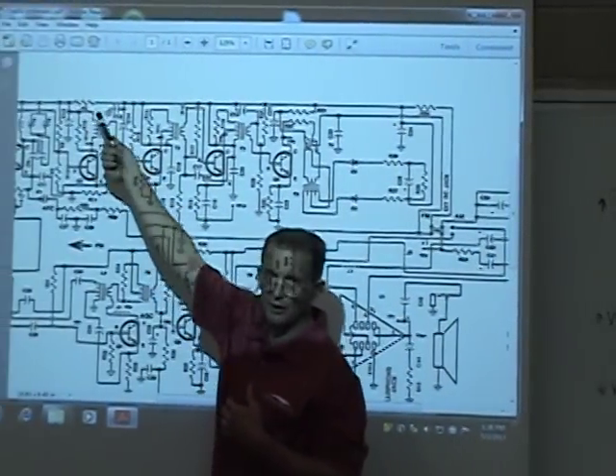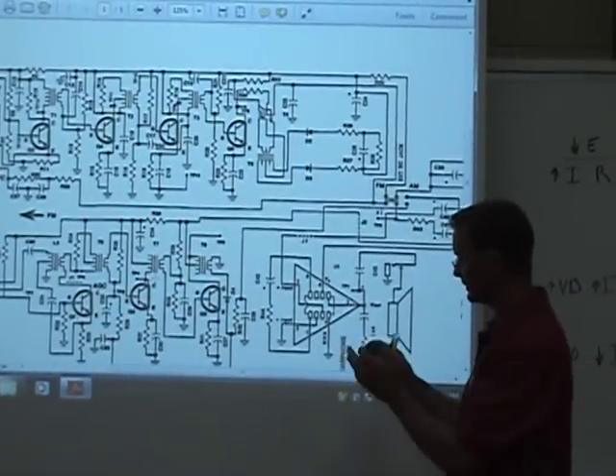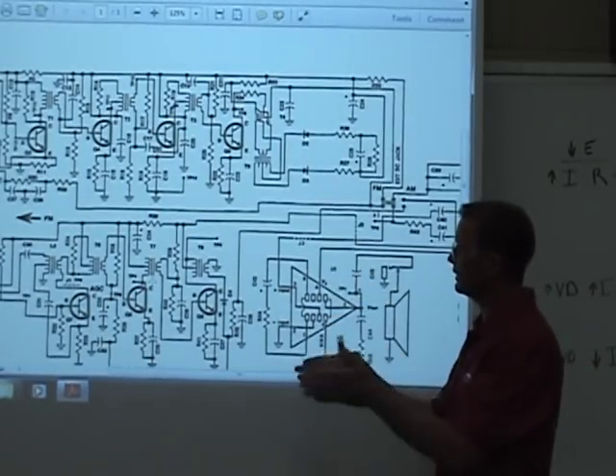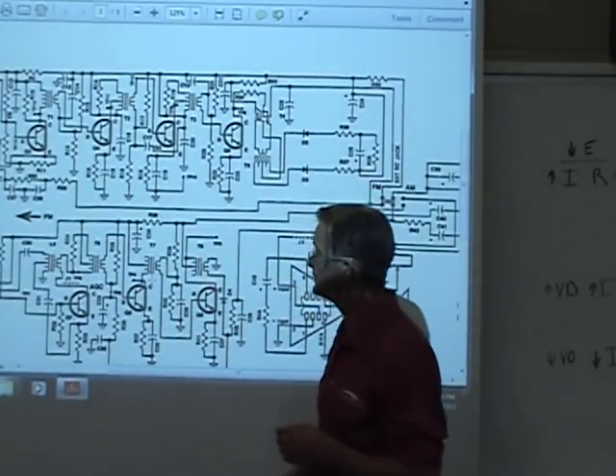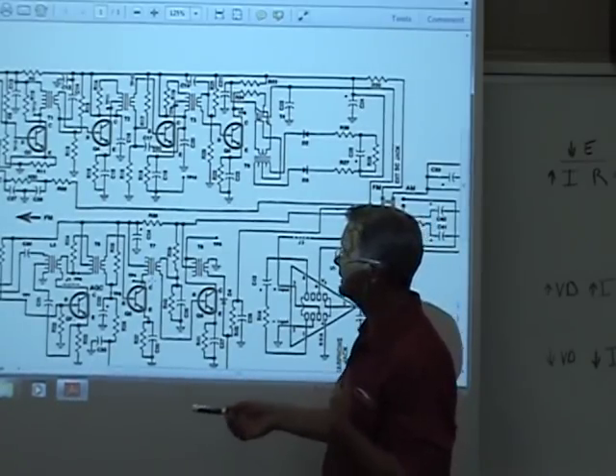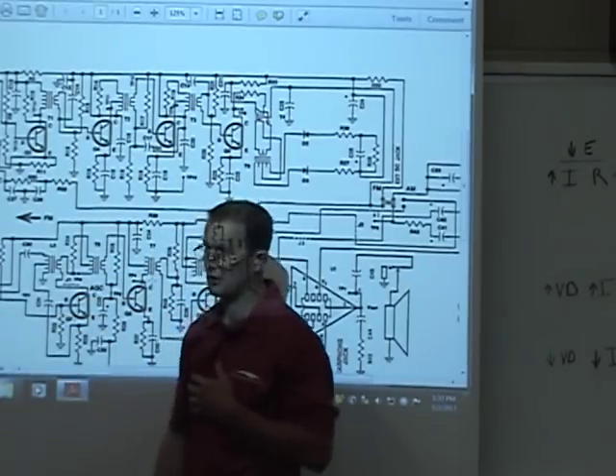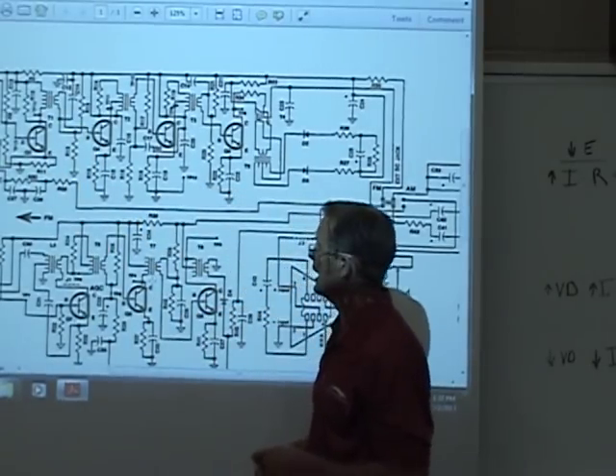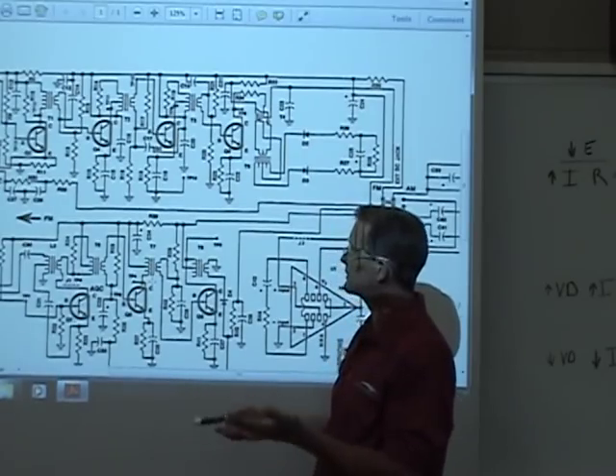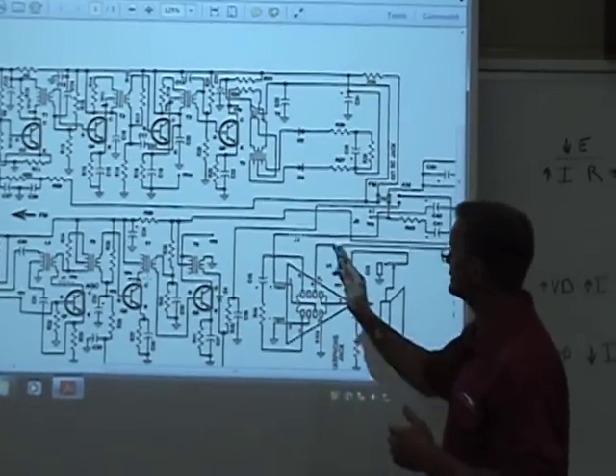One of the things I'm going to do is I've found that I'm going to quickly go down. I'm going to follow my line. I'm going to come down to R9. As I get to R9, I'm going to check for a voltage drop. I'm going to check my good system. I'm going to check my troubled system. And I'm going to look at it and I'm going to say, if I tend to have a pretty excessive drop on R9 too, then what I'm going to be looking at here is more than likely my short or my leaky system, my bad resistance is on that side of R9. In this case, we're going to say it wasn't exactly the same voltage drop, but it wasn't excessive. So what I've typically found is that it's going to be apparent whether or not it's on one side of R9 or the other. We're going to say it wasn't excessive, so we're going to concentrate our efforts on this system.